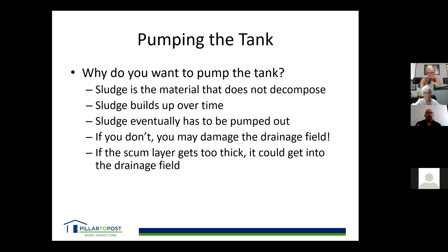Another reason to pump is if the sludge layer gets too thick. In the city, people often pour cooking oil — like bacon grease — down the drain, but on a septic system that can cause real issues. We already get enough fats and oils from our waste and showering, so we don't want to introduce extras. Once the scum layer gets too thick and grease and oils reach the drainage field, they congeal, coat the inside of the pipe, and it stops draining. The only fix is chemicals or high-pressure hoses, which are very expensive.